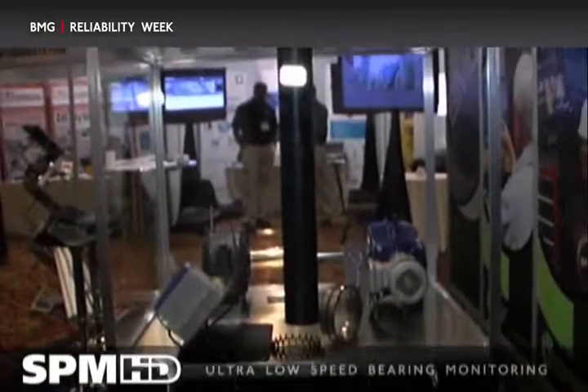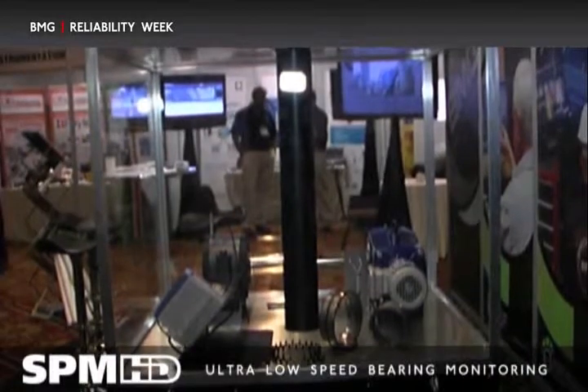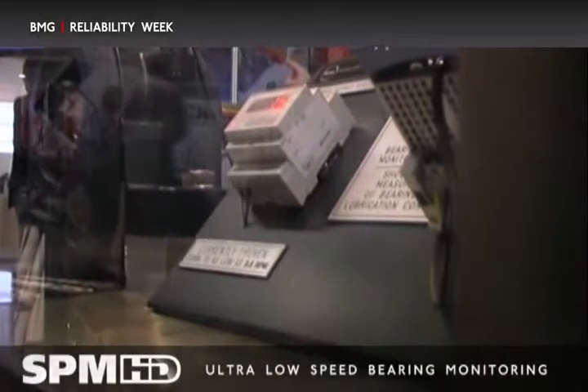One of the key developments recently unveiled in Europe with our supplier SPM Instrument in Sweden is their new SPM HD system. It's a groundbreaking system that nobody else can supply. It focuses on monitoring equipment that runs at very low speeds, down to as low as 1 RPM. We're talking about drum reclaimers, bucket wheel reclaimers, bucket elevators, low-speed conveyors, agitators and mixers. There are many applications we can look at.